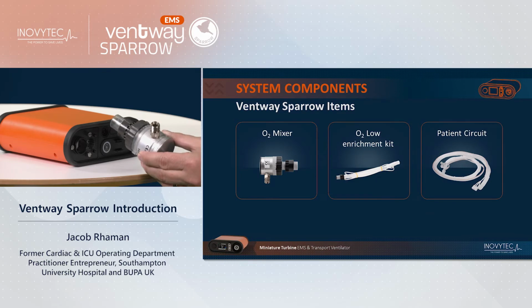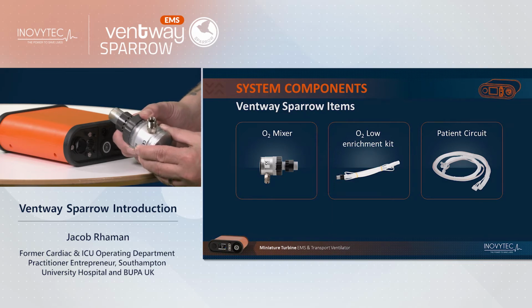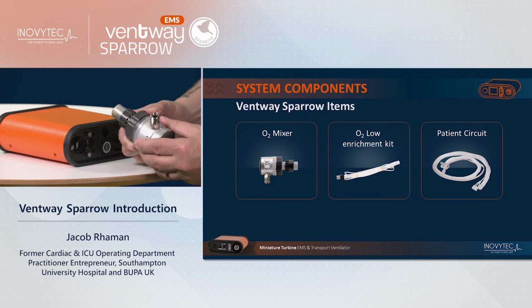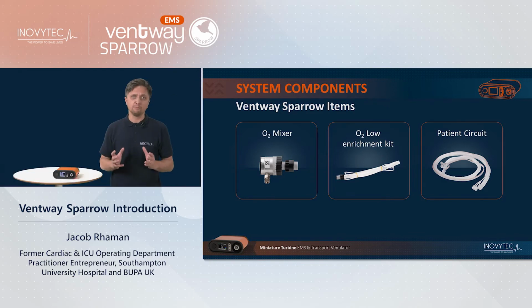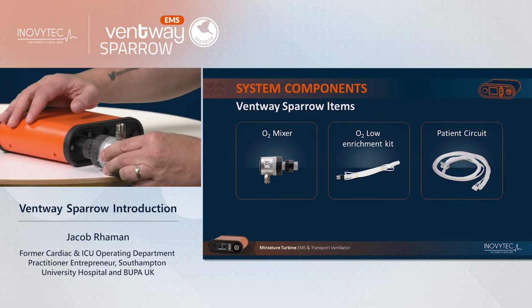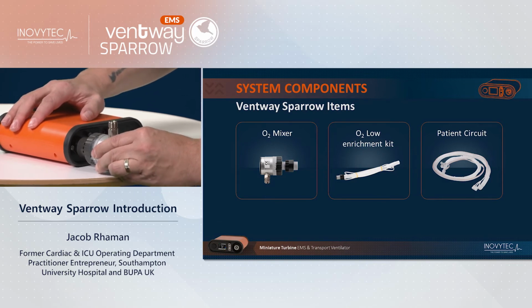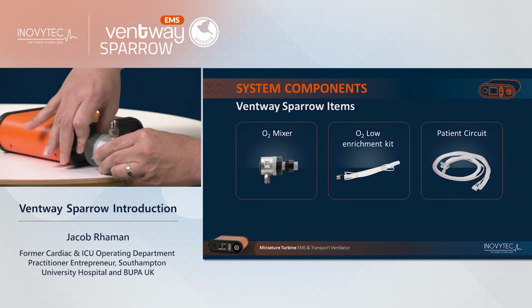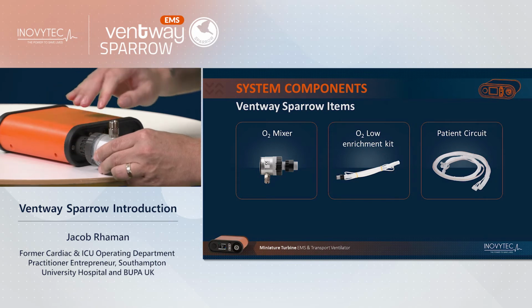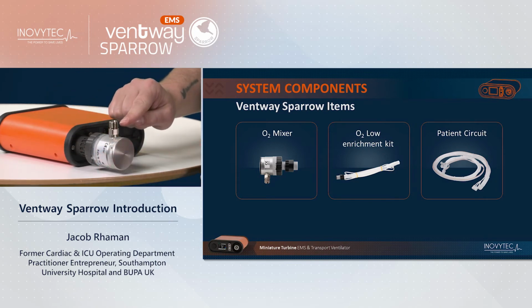2. To use high-flow oxygen for the Ventway Sparrow, Inovytec also supply an oxygen mixer. The oxygen mixer can supply different levels of oxygen, ranging from 30 to 90%. This can be set by simply turning the dial to the desired level of oxygen. The oxygen mixer is connected to the rear of the panel and secured using the safety ring. The oxygen mixer can then be connected to an external piped oxygen source, so high-flow oxygen therapy can be applied.